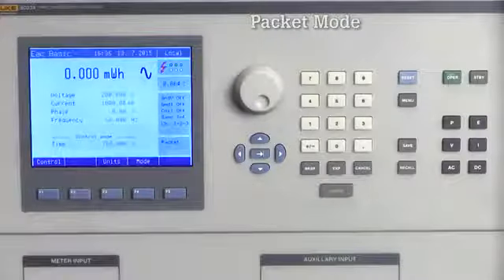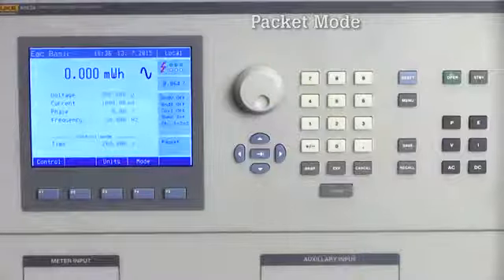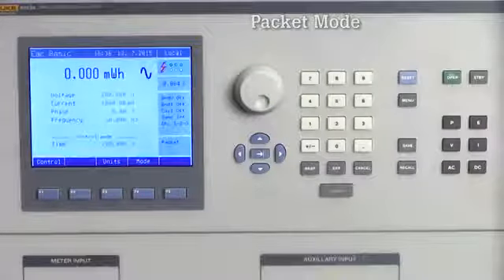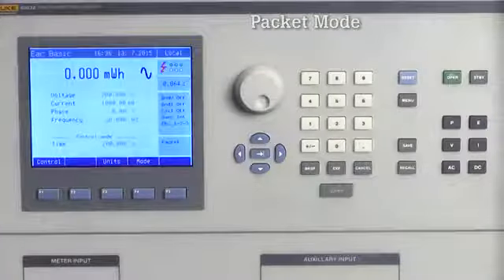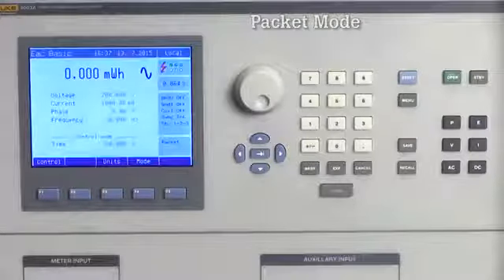I've configured my test for 200 volts, AC, 50 Hz, and 1 amp. I'll set the packet time for 200 seconds. I've also prepared the meter to start measuring from 0. I will now push operate and you will see that the test starts and the countdown begins.